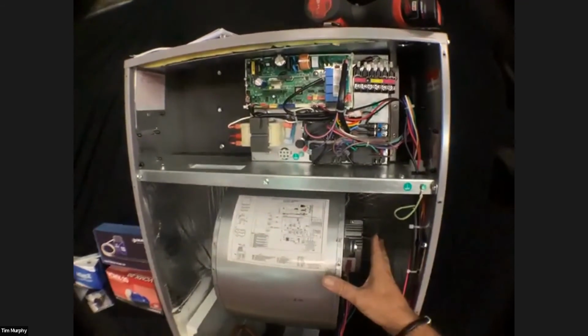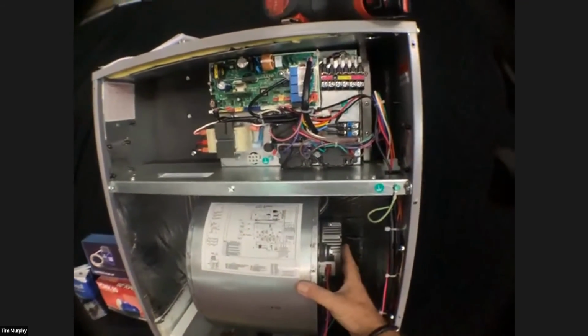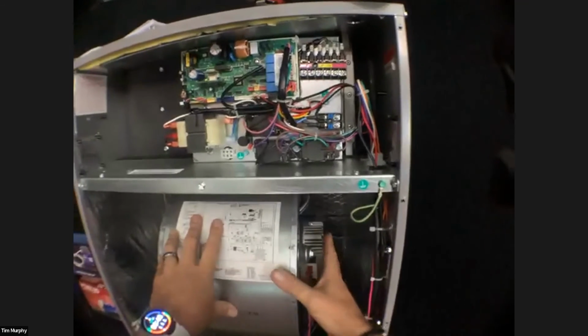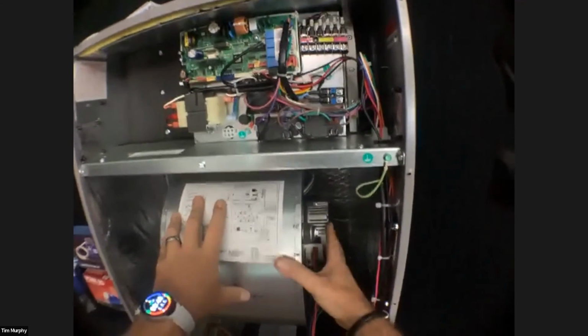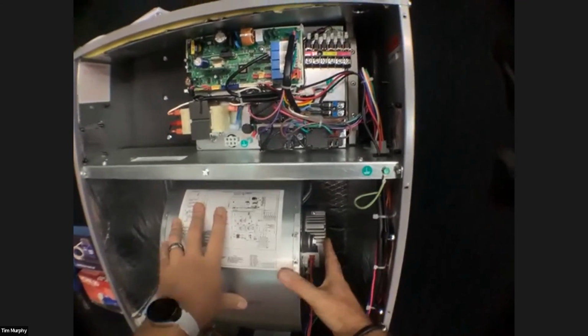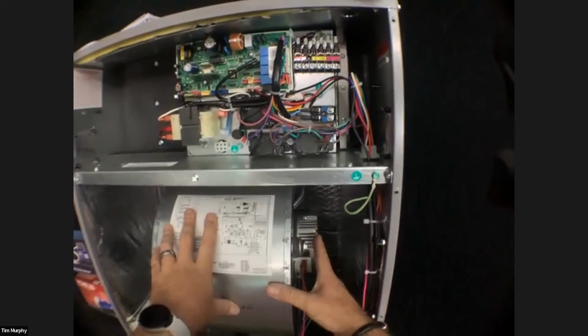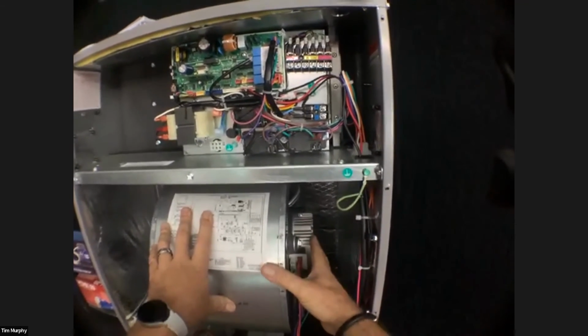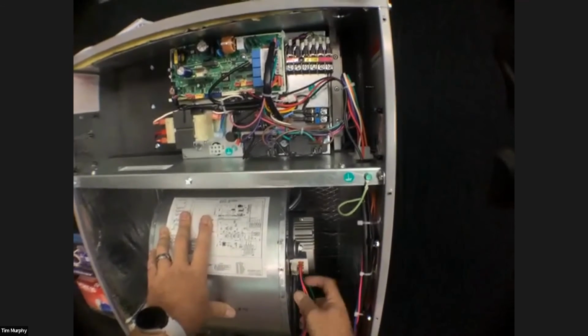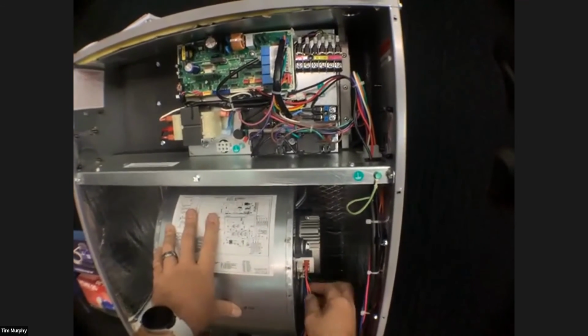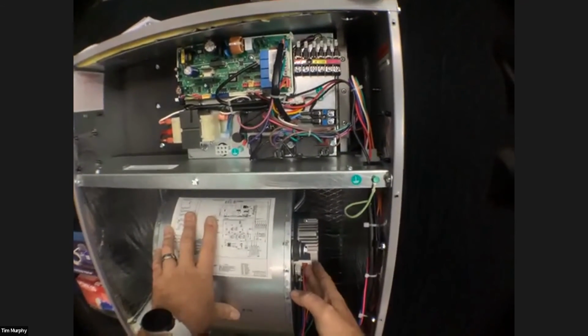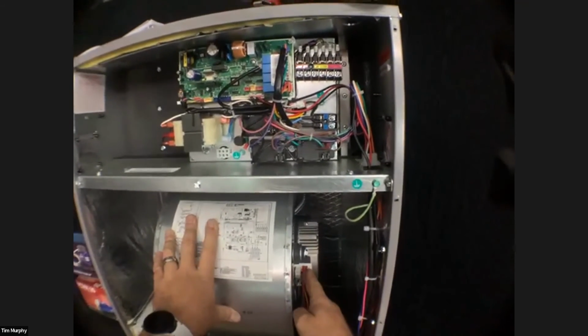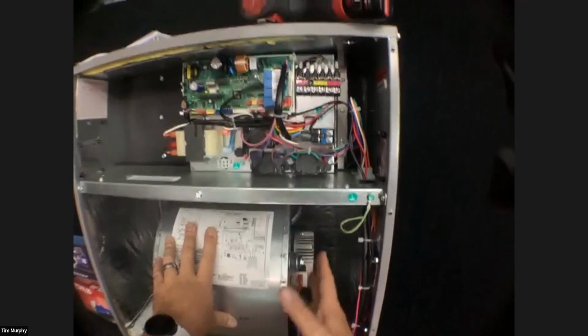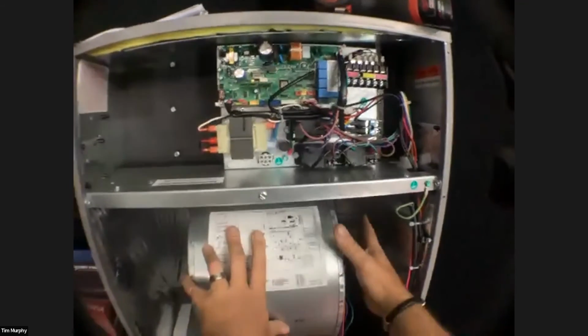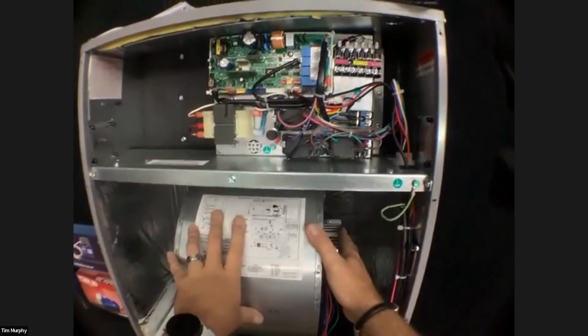But the good thing about this is that if you run into an issue later on down the road, hopefully you don't, where you have a failed fan motor, you can essentially use a rescue motor that would replace a standard X13 style motor, and you could troubleshoot it just like you would any X13 motor. You could check for your line voltage, and you could check for your low voltage when you get a call for cool. So that makes life a little easier when it comes to finding replacement parts for this system.